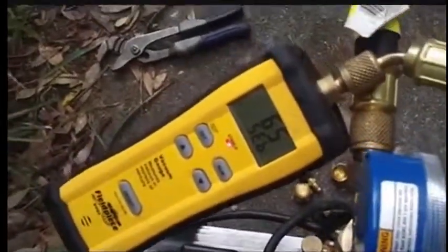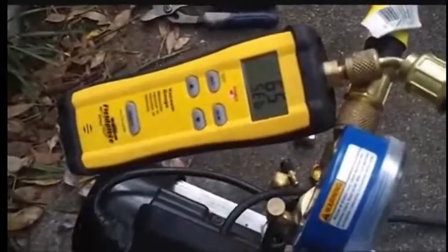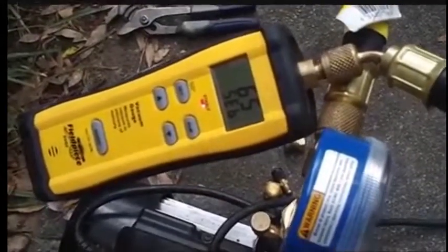Alright, we pulled the vacuum. The pump's running down to 65 microns, which is pretty daggone low. The pump really does a great job. My old setup with just the gauges running the vacuum would have never made it down this far. It might have, but it would have been like a year or two from now. This happened in half an hour. So it's kind of bottomed out as far as it's going to go, and we're about done here.